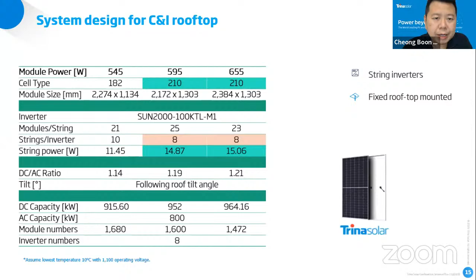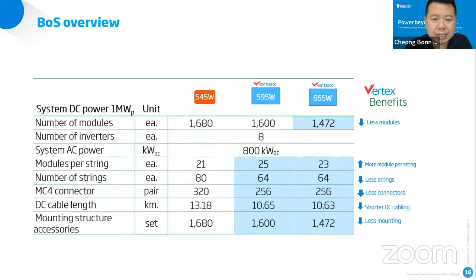This is the overall balance of systems overview. As the number of modules per string increases, we have fewer strings, so we use fewer connectors, shorter DC cabling, and fewer mountings. All of this translates to savings at the system level.